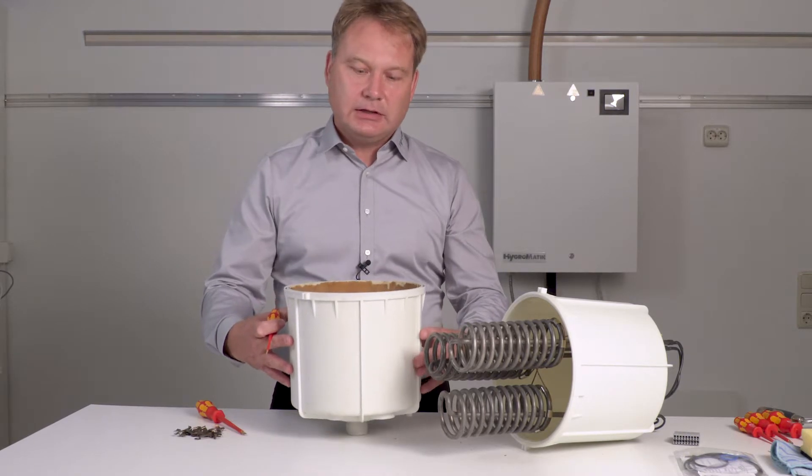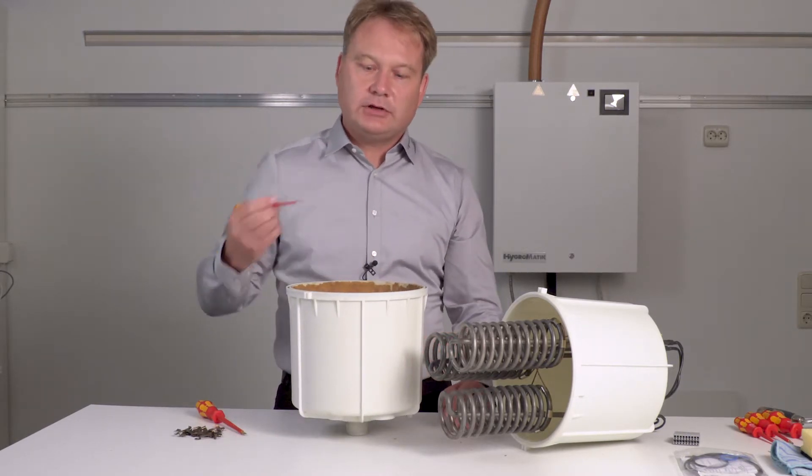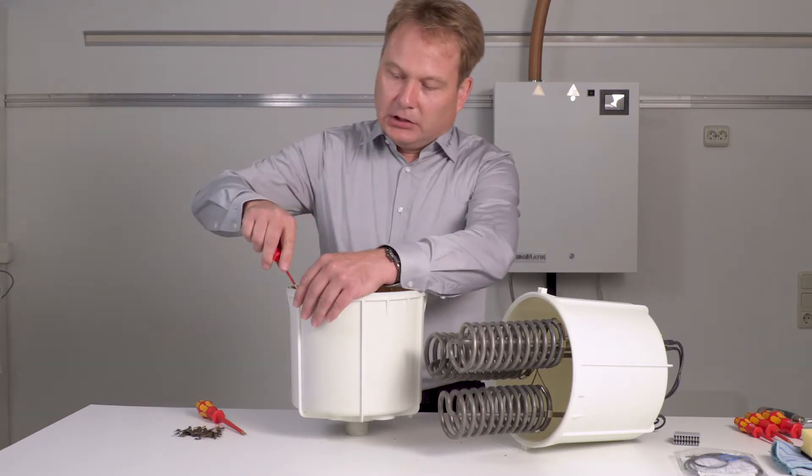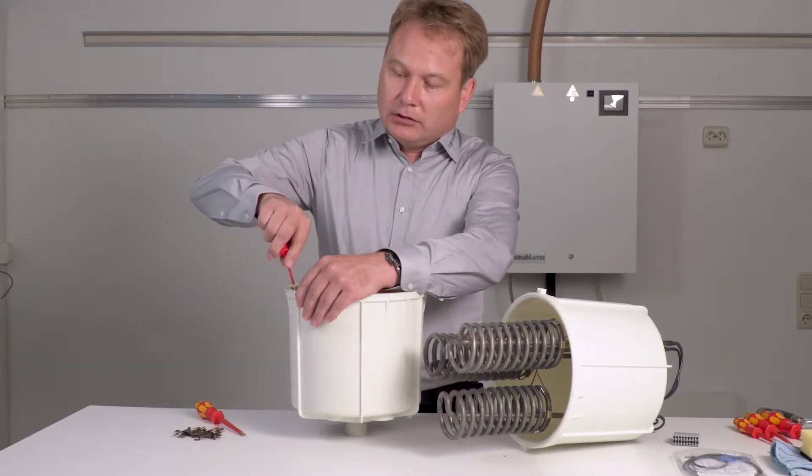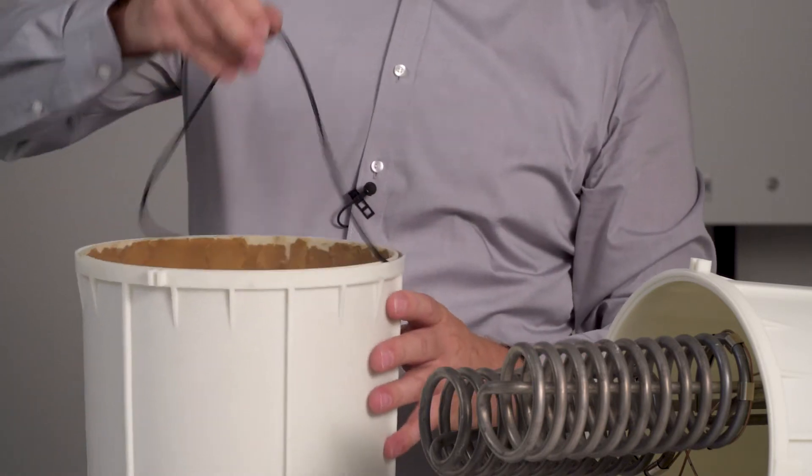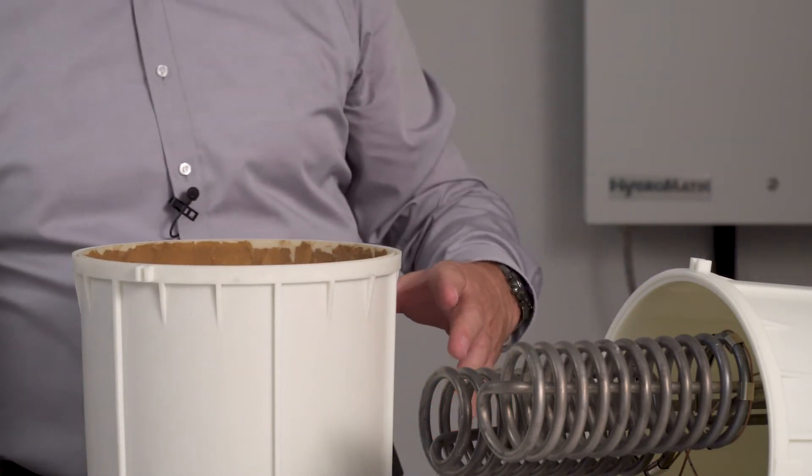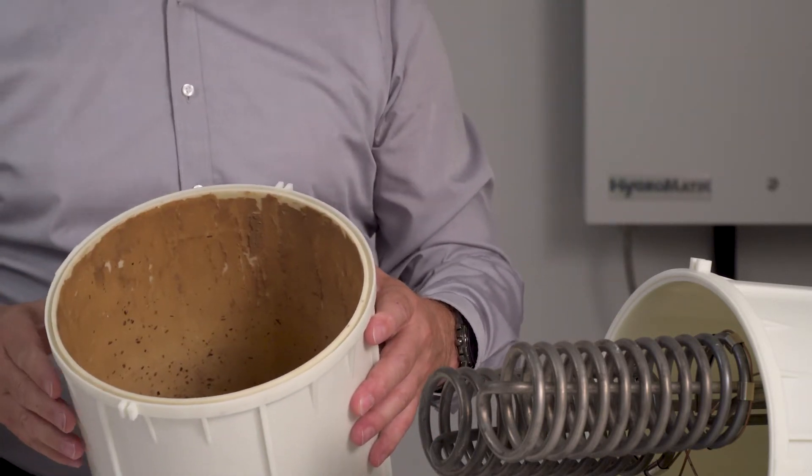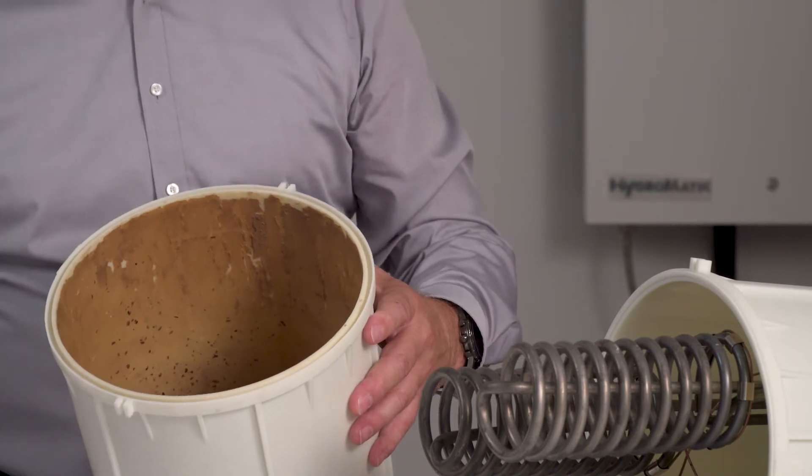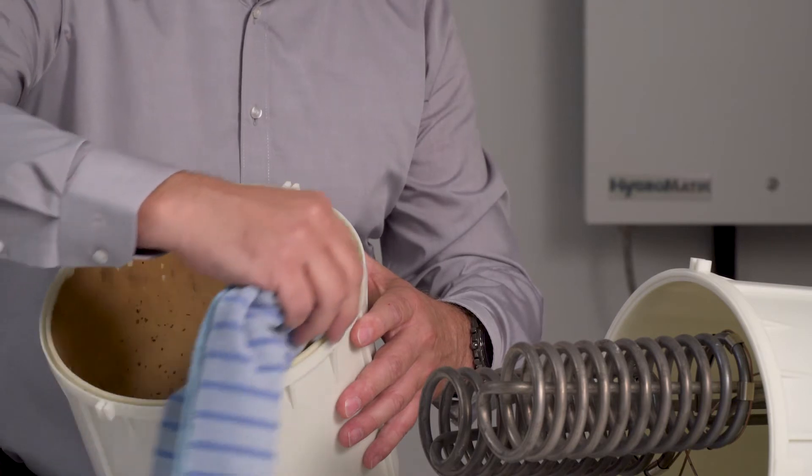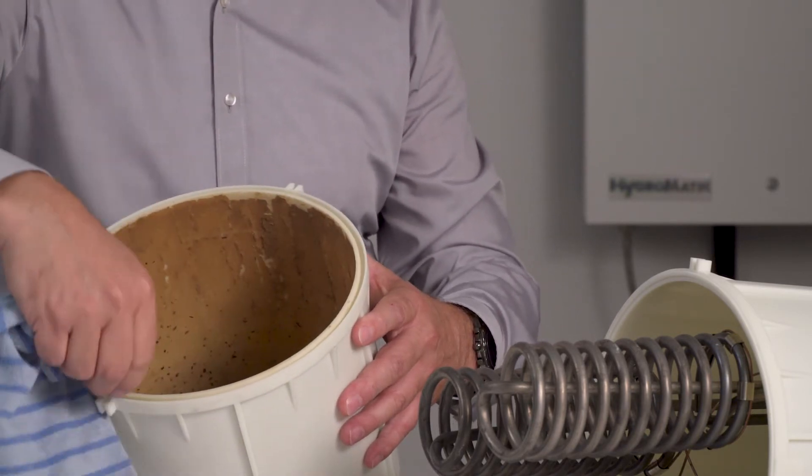Next, the cylinder flange O-ring is removed. I use a small screwdriver and lever behind the O-ring. I lift this O-ring out of there. The surface of the seal must be absolutely clean. I use a small cloth and clean the surface of the seal, the groove in this case.